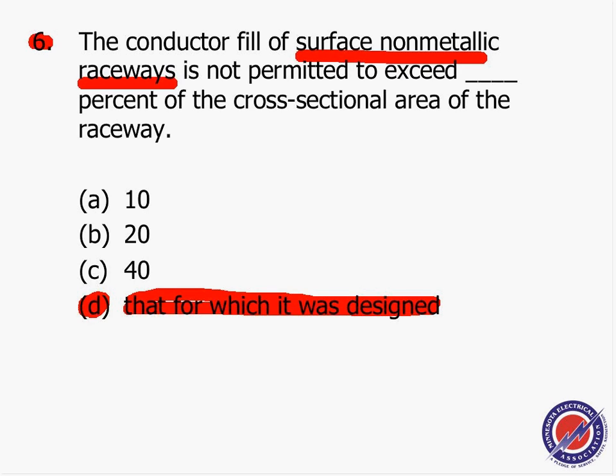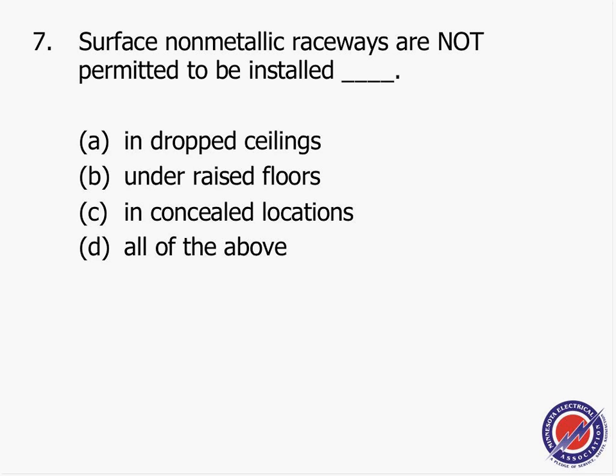I think there is a condition, Brenna, my friend, if you fill 20% and if the cross-section area was, I think, 4 inches or larger, and these are for the metallic anyway, and if you maintain 30 current carry conductor or less, then you don't have to derate. But then for derating, how many conductors can I put in a non-metallic raceway? As many conductors as the manufacturer allows us to do so. So don't get confused between the 20 that comes from the wireways. That's probably why a lot of you guys got that one wrong, because you get confused between wireways and raceways.